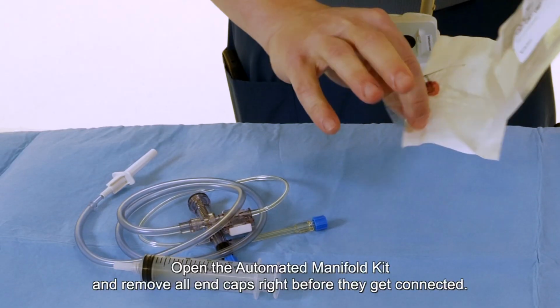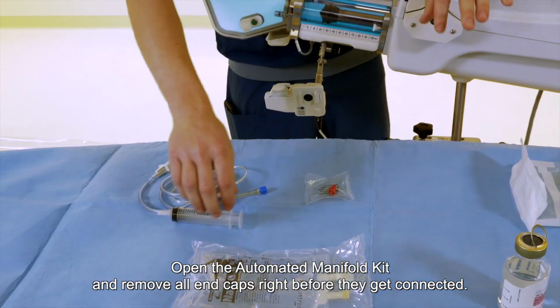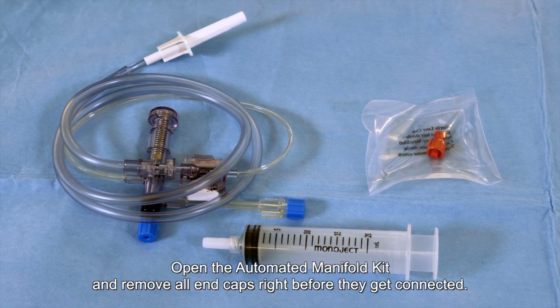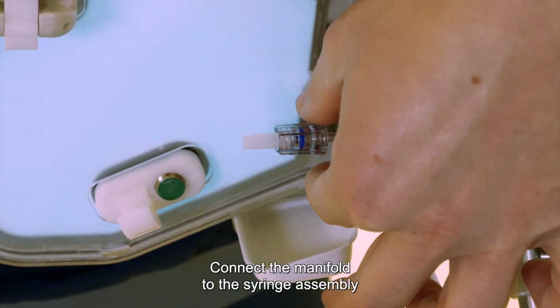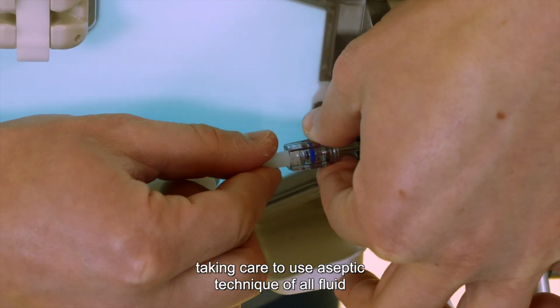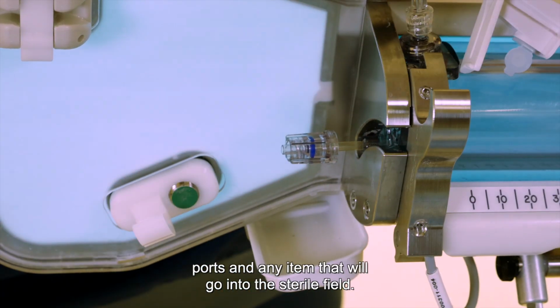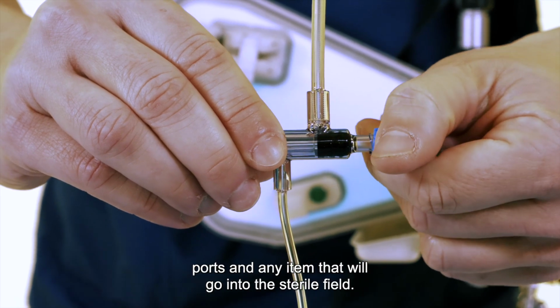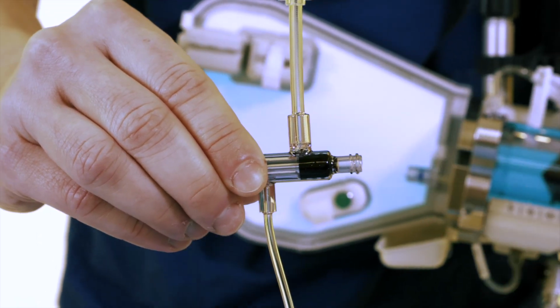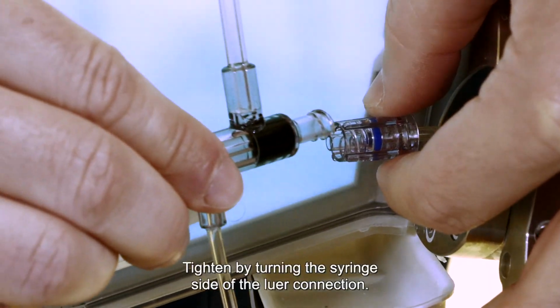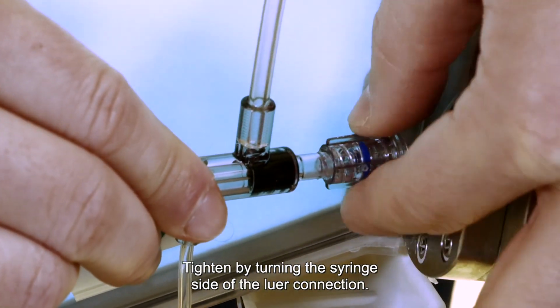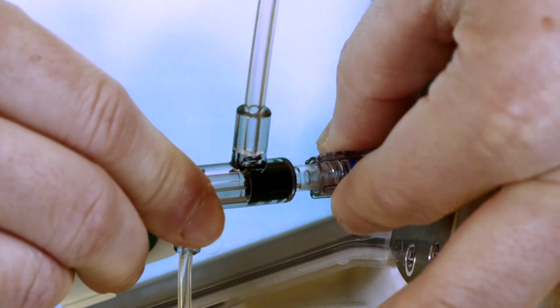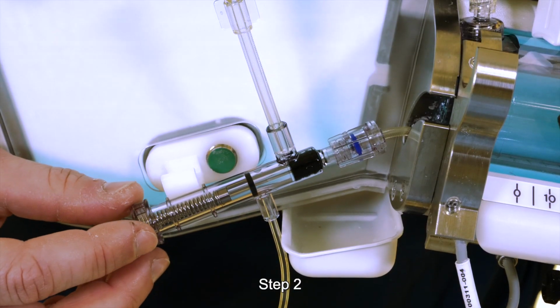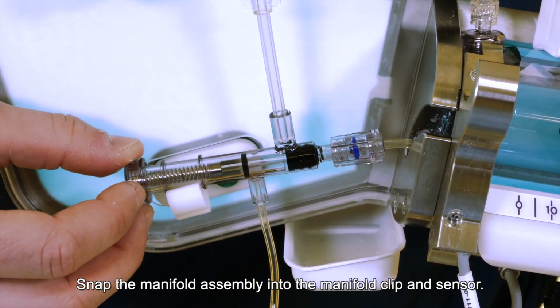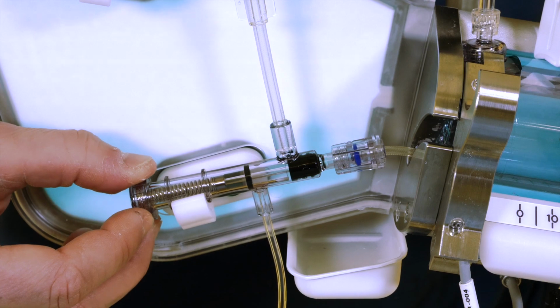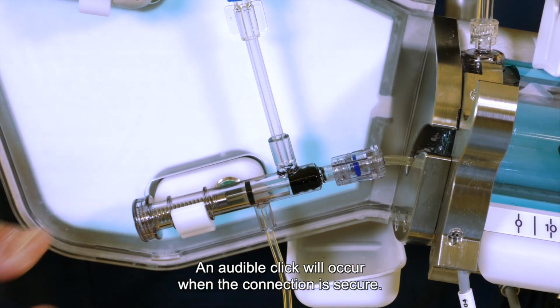Step 1. Open the automated manifold kit and remove all end caps right before they get connected. Connect the manifold to the syringe assembly, taking care to use aseptic technique on all fluid ports and any item that will go into the sterile field. Tighten by turning the syringe side of the luer connection. Step 2. Snap the manifold assembly into the manifold clip and sensor. An audible click will occur when the connection is secure.